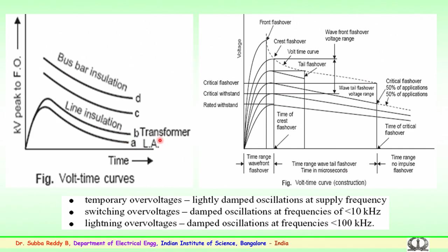the equipment. So, in the previous slide we have seen the case of the transformer and the lightning arrestor. The lightning arrestor should act before the lightning insulation strength of the transformer is reached. So, to protect the transformer, the lightning arrestor is used, so that the breakdown strength of the lightning arrestor is slightly lesser than the insulation strength of the transformer. That is the information which has to be known.